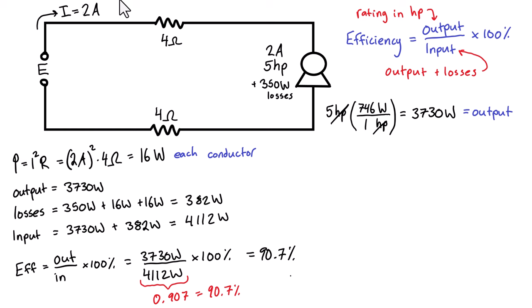But that's how you calculate the circuit efficiency. You have to take into consideration the losses of the motor itself and the losses of the rest of the circuit, usually being the conductors. Line losses in the conductors or if there's something else specified in the problem, then you'll need to take care of that as well.